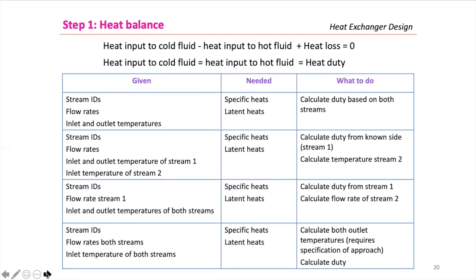Step one is setting up a heat balance: heat input to cold fluid equals heat input from hot fluid equals the heat duty. A guideline table shows how to approach different cases — for example, if stream IDs, flow rates, and inlet/outlet temperatures are all given, you need specific heat and latent heat from tables, then calculate the heat transfer rate from both streams. These are guidelines only.